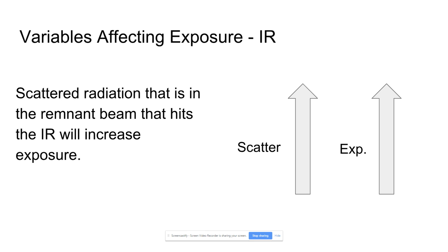So the only time you might have an issue in digital imaging is if you would have needed much more exposure, right? Because then you'll get noise because it can't compensate. But for example, this is not particularly good, but if the patient, let's use the example before, has osteoporosis, which would require a decrease in the radiation, let's say you don't do anything, just shoot it like any other image, or that patient data wasn't even there at the time, it'll fix it, right? Because digital imaging does good with overexposure, not so good with underexposure. Underexposure leads to noise and a grainy image.